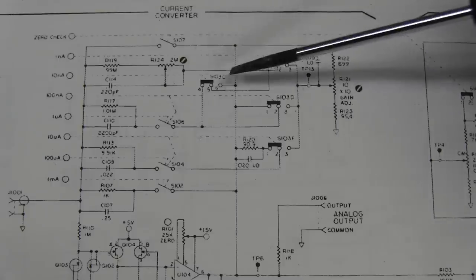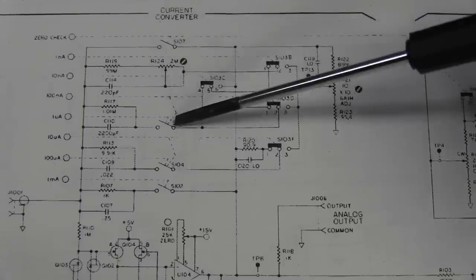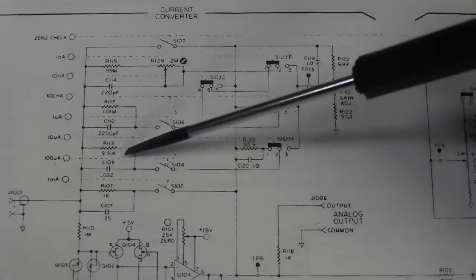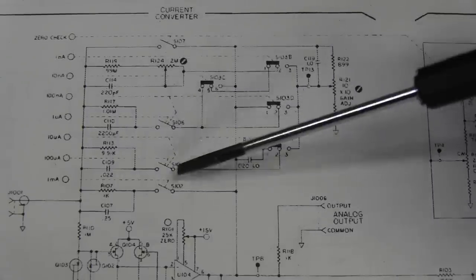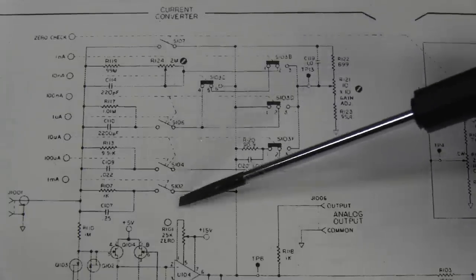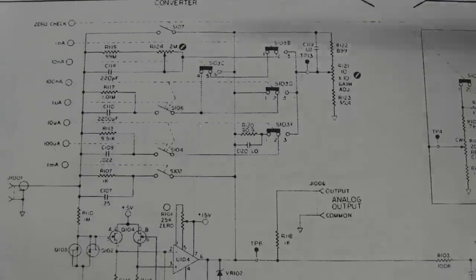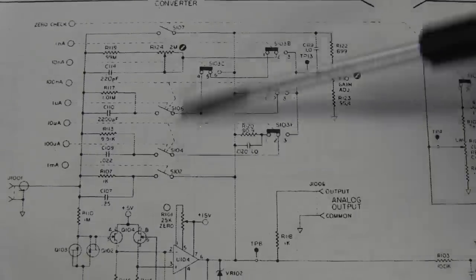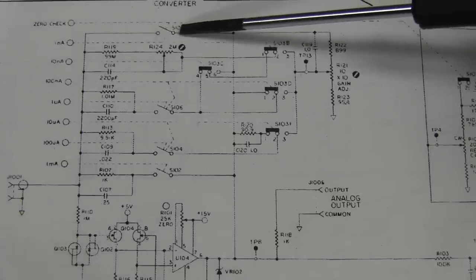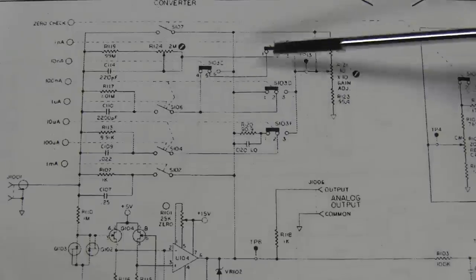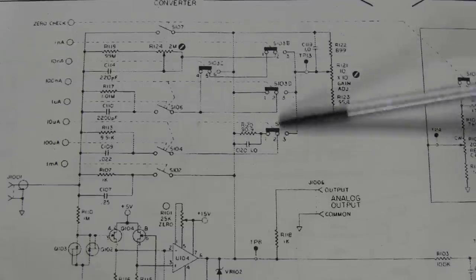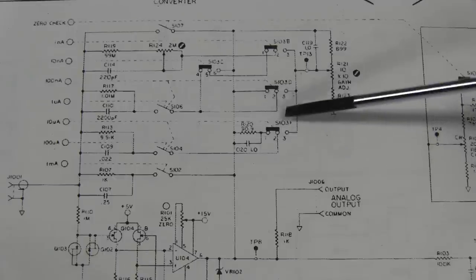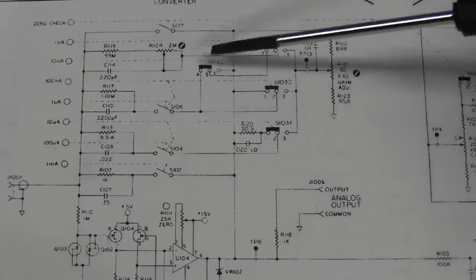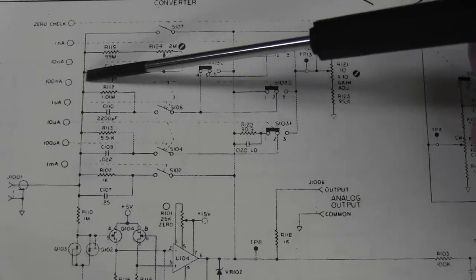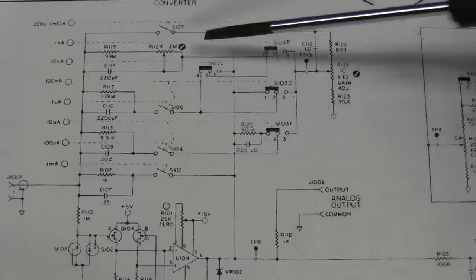Here you go. You can see the switch contacts in the feedback path there for the feedback resistors. There they are, your gold leaf contacts, and they have to be incredibly reliable, incredibly low noise contacts when you're talking about an instrument of this caliber. And if you notice, before we had four of those gold spring contacts, and there's the four contacts, and they've also got some of the other range switches here, which is switching some more non-critical stuff. And you can see that the 10 nanoamp range and the 100 nanoamp range aren't actually switched at all, as we noticed inside the unit.